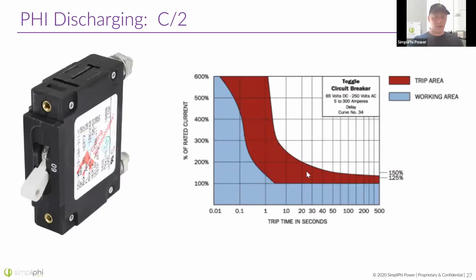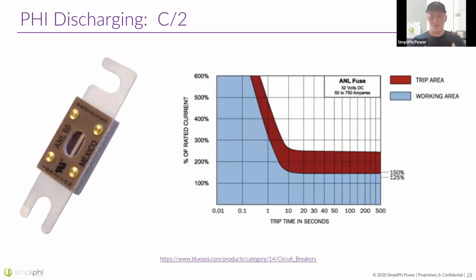For example, though, this breaker claims to open circuit exactly at 100% of the rated load in as little as about 5 seconds. A little bit hard to believe, but that's a nice breaker. Now, this fuse is not going to open circuit until you're at about 140% of the rated current, and it's going to take, again, up to maybe 10 minutes to do that. So if we're looking at 140% times 60 amps, that's 84 amps. This would not be an applicable fuse to use for overcurrent protection for that style system. So that's why I say that this is not always a good solution. It requires a lot of research and things can vary. The best solution is just sizing your battery bank to meet the needs of the inverter charger and charge controllers.